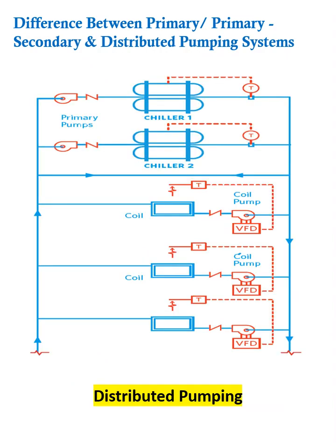The third system is the distributed pumping system. Here, the primary pumps remain, but the secondary pump that was typically centralized has been relocated to the load side — the AHUs or different buildings where chilled water is being pumped. Instead of having one large secondary pump, the requirement is split across multiple applications, and pumps are designed and incorporated based on each application. This saves a lot of energy and reduces investment costs. This configuration is called the distributed pumping system.